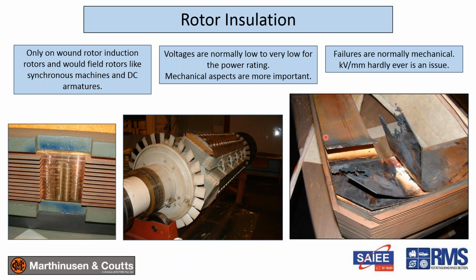It was due to dust, gas, sulfur in the gas, sulfur gas in the air in the plant, eating away at the brazing. But you can see here the insulation between turns would be less than 1 millimeter, and the main insulation would protect the winding from the core. But the main insulation would be very thick, much thicker than the inter-turn insulation, probably of the order of 2 millimeters, let's say. But for that voltage, it's actually overkill.